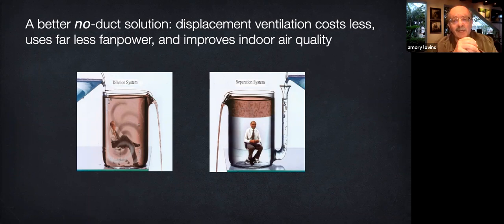Wouldn't it make more sense, as on the right, to supply clean air at or near floor level and let it gently push the dirty air out at the top so you're breathing only clean air all the time? And wouldn't that make even more sense if your building isn't all passive or radiatively cooled, so you're having to supply moderately cool air, which rises as it warms? This is the principle called displacement ventilation.